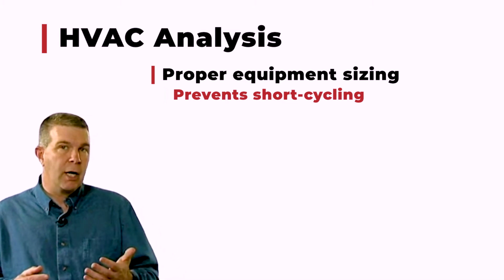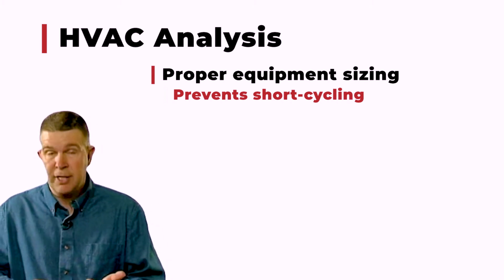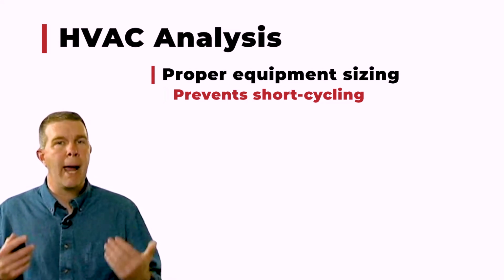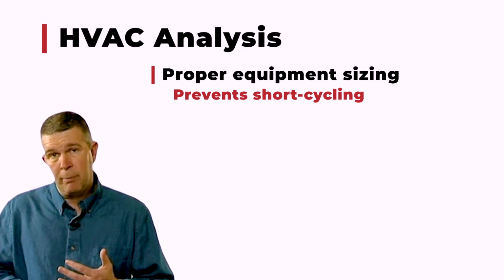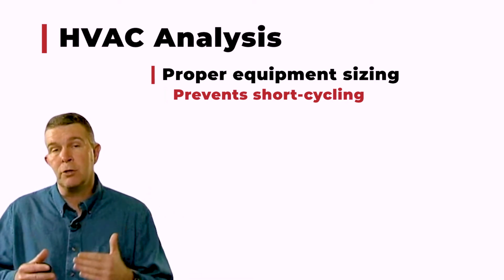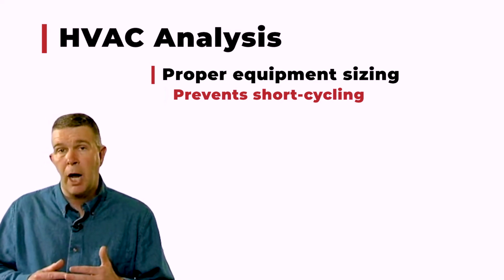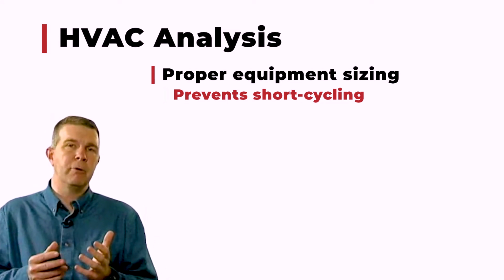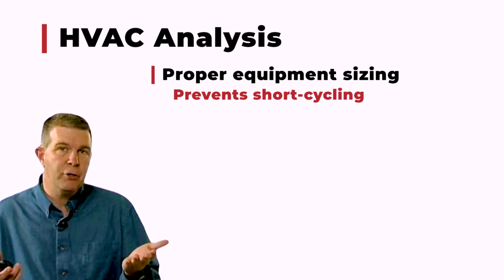If it's properly sized, it'll turn on and it'll run at steady state. Steady state is what we want to run it at, because at steady state you have better efficiencies, you're going to wear it out less, it's going to be a happier piece of equipment. And most important, if you oversize this piece of equipment, think of it this way. You have a big, large air conditioner that turns on and very quickly drops the temperature of your structure. Well, most air conditioners only operate off the sensor of temperature, not off of humidity. But you have to remember that an air conditioner works to solve both issues, temperature and humidity.